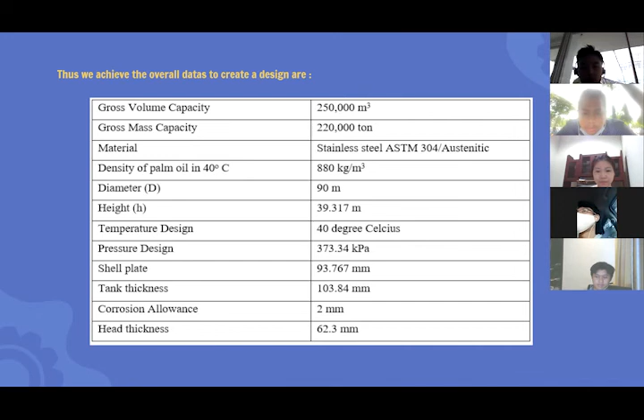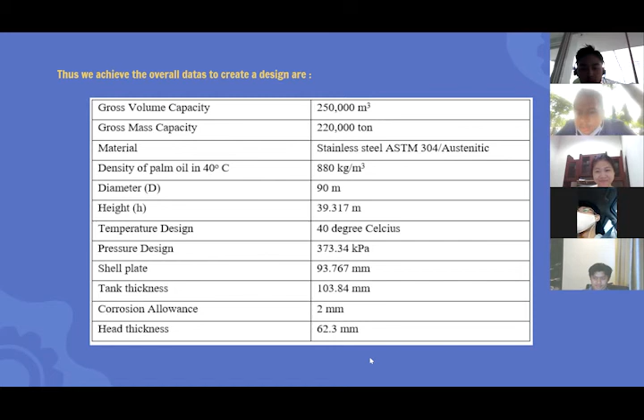And the density of palm oil at 40 degrees Celsius is 880 kilograms per cubic meter. The diameter is 90 meters, and the height is 39 meters. For the design temperature, we use 40 degrees Celsius. For the design pressure, we use 373 kPa. For the shell plate, we use 93 millimeters. The tank thickness is 103 millimeters, the corrosion allowance is 2 millimeters, and the head thickness is 62.3 millimeters.